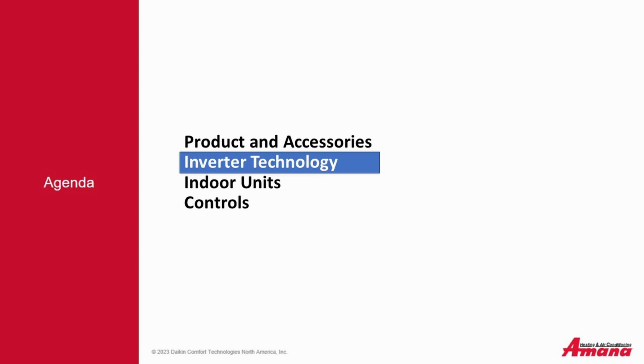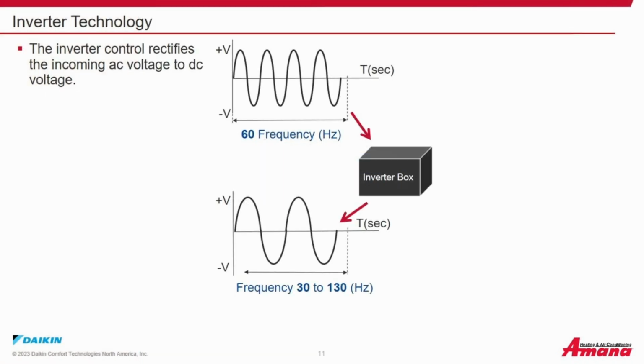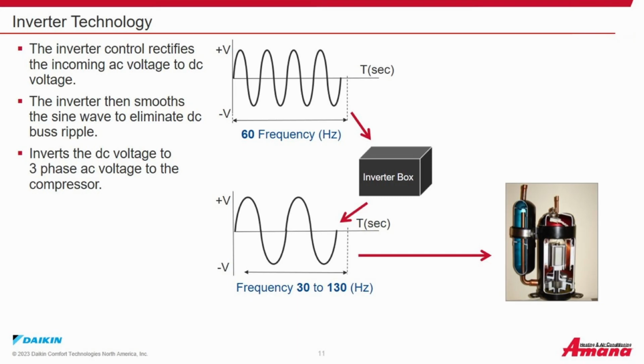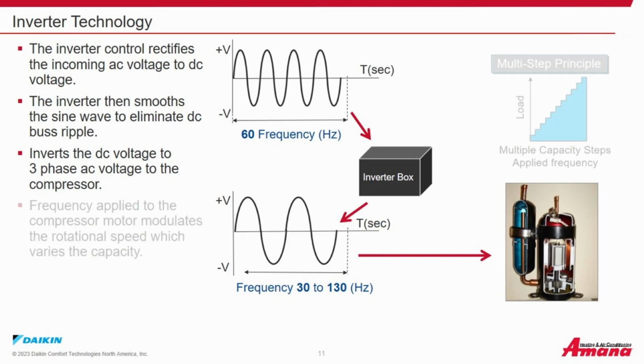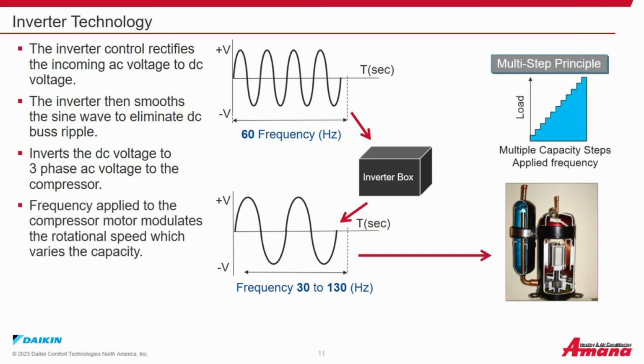Inverter technology. The inverter control rectifies the incoming AC voltage to DC voltage. The inverter then smooths out the sine wave to eliminate DC bus ripple. It inverts the DC voltage to three-phase AC voltage going to the compressor. The frequency applied to the compressor motor modulates the rotational speed, which varies the capacity of the compressor.